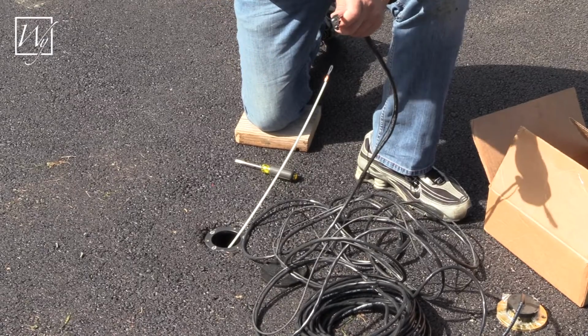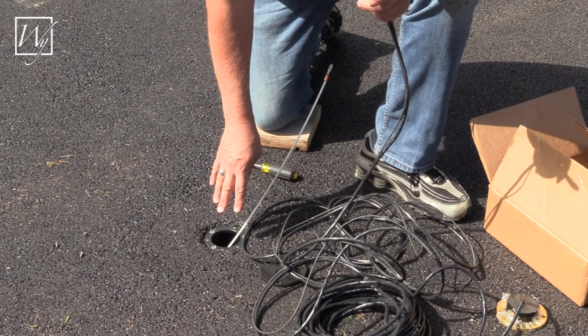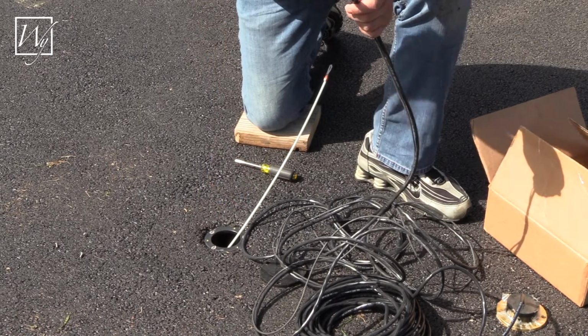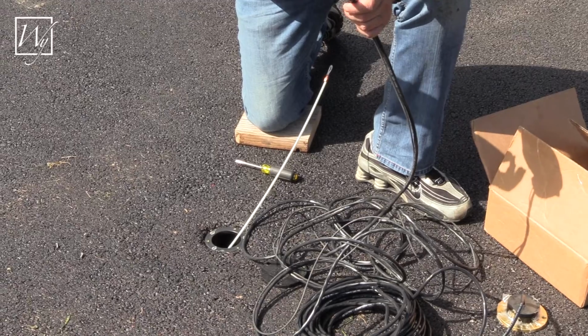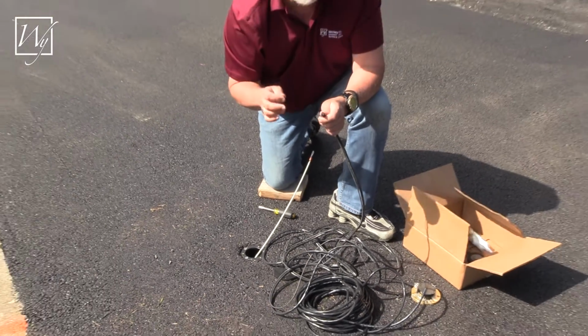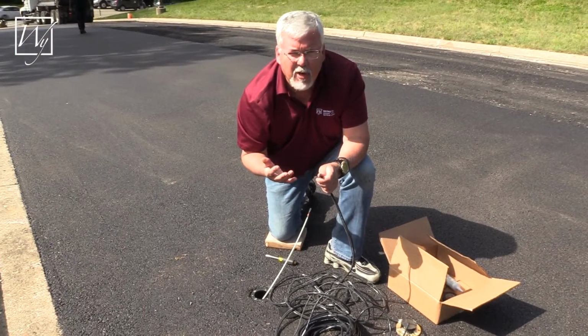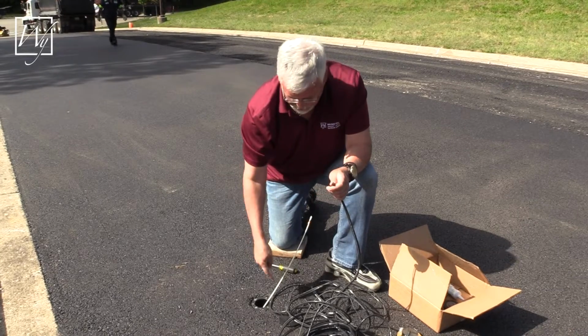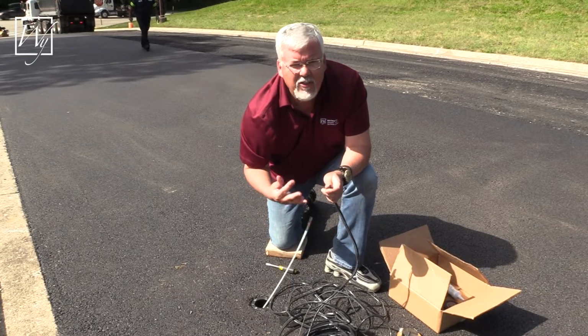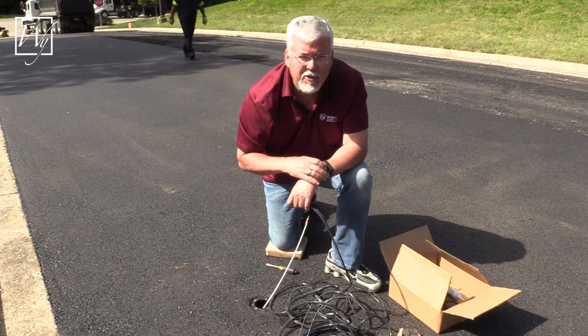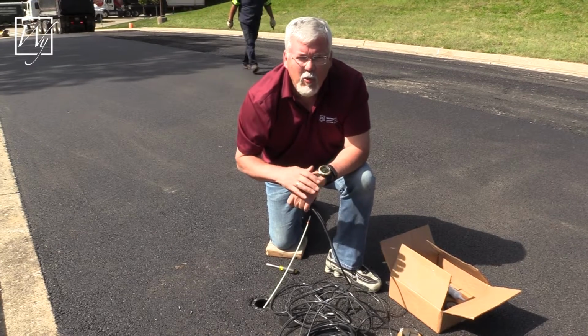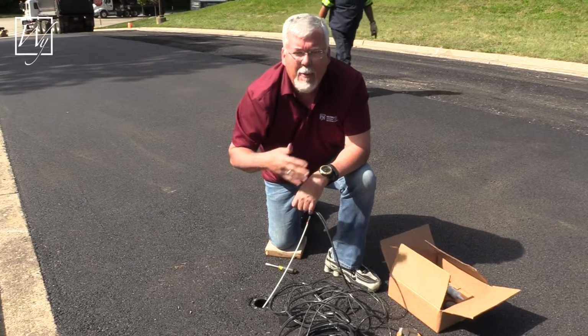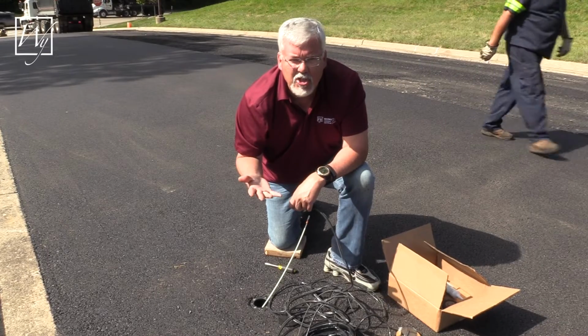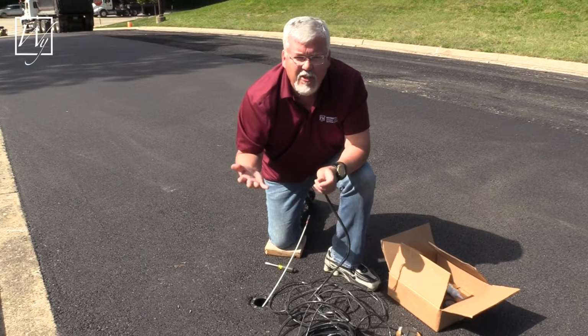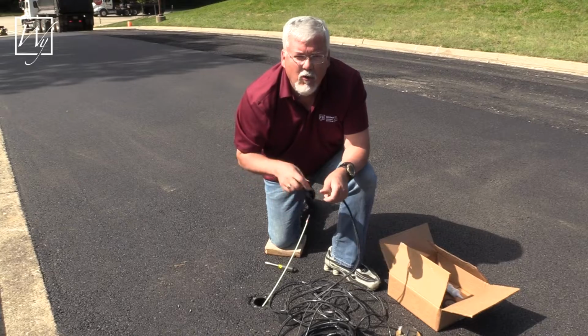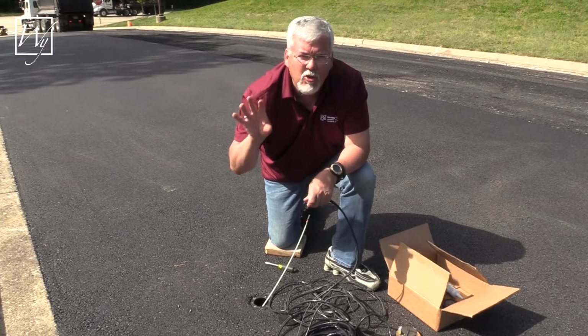We're actually going to have two sensors in here. One is the asphalt sensor, which tells the controller when the temperature gets below 38 degrees, or whatever the set point is, and whether precipitation is present. There's also a sensor placed a bit further along, the over temperature sensor, which tells the controller when the slab reaches a certain temperature so it can shut off at 60, 50, or 70 degrees, whatever that number is set to.